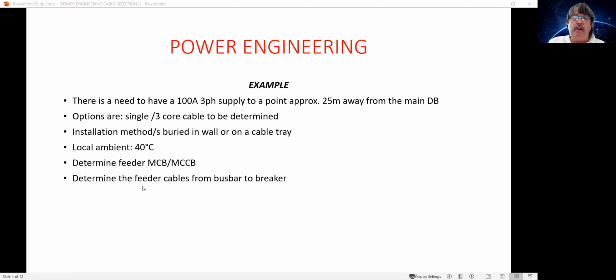If we look at these installation methods, could be buried in a wall, underground, or on a cable tray. And why I've done that is because these two options highlight some of the issues with the cable selection. We've said the local ambient is 40 degrees. Important to know that because that plays a part in the cable selection as well. And we're going to try and determine some feeder miniature circuit breaker or a molded case circuit breaker. And in this case, we're not really going to look too much at the bus bar to breaker type cable feeders to that, but we will just make some comment on what we have there.